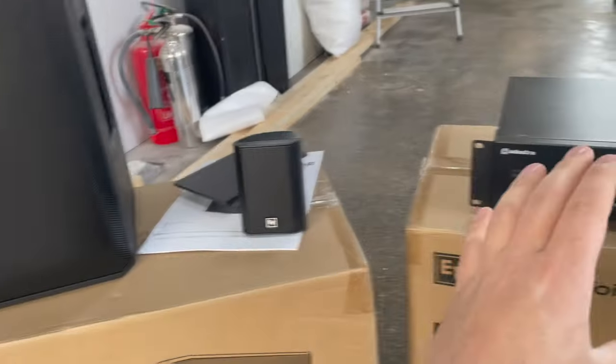Just thought I'd show you a bit about how we put sound systems together. We're putting a background system in this restaurant - background, a bit of foreground. We've specced it quite well: two subs and four speakers. If you don't know how it works with amplification and speakers - we're not using a 100-volt line. A 100-volt line is for running long distances to get around volt drop and cable resistance. You can have multiple speakers on a 100-volt line, it keeps going and going, but it's not as loud and the sound quality can't be quite as good. You often find that in supermarkets for announcements.